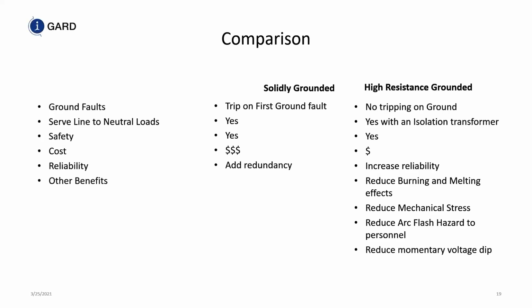So if you have a transformer, employing a resistance grounded system is more cost effective than a solidly grounded system. That's what I'm saying. If you are getting 600 volts or 480 volts from the utility directly and you have no control over the transformer, you're going to get whatever they give you. You have no choice at all. I hope that answered your question?